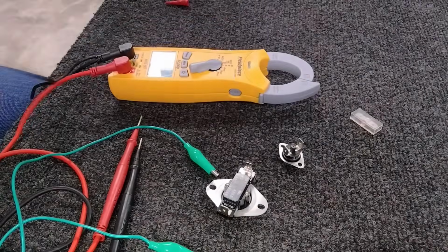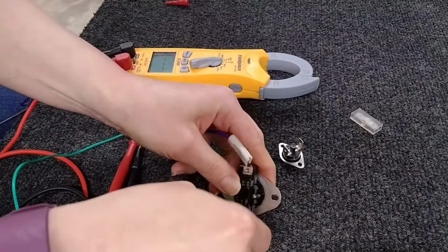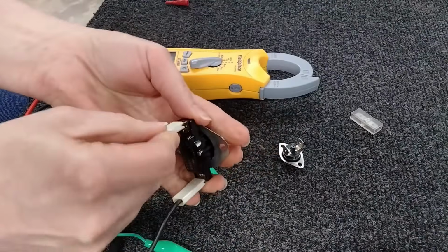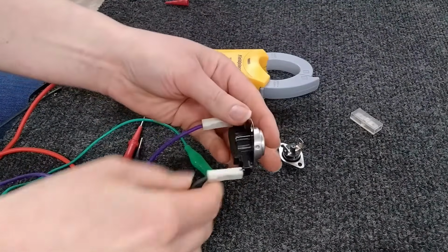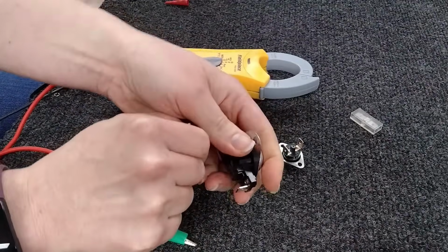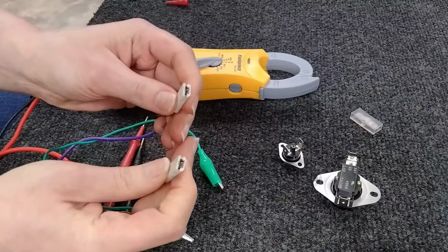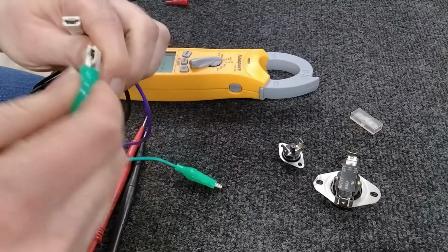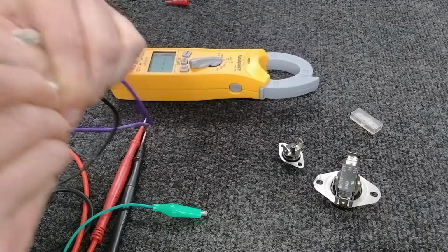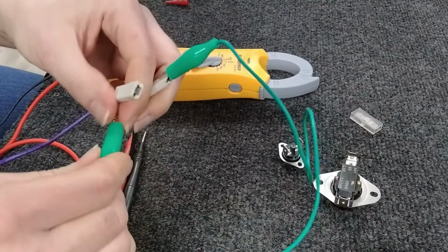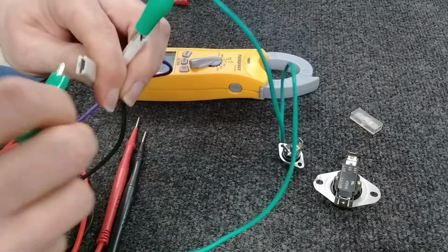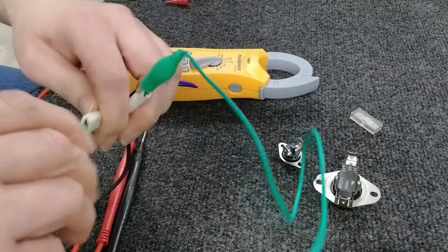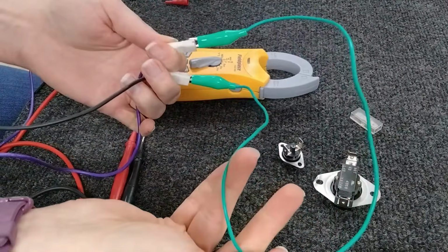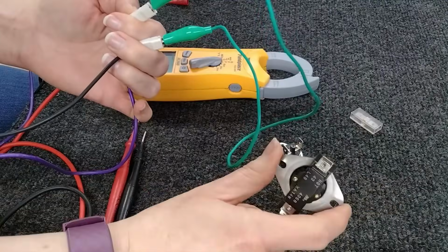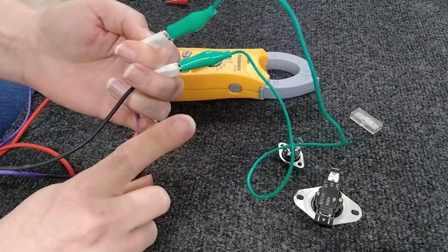Pull your wires off, because they're going to be connected here on either side. Great. So you're going to remove those wires, and what this is doing is closing the circuit yourself. Here we can just hook our gator clips on there, and these next ones are super annoying because they've got these little insulated tabs on them, which is super fun to try to hook anything on. And now we've effectively closed our circuit. So it's going to bypass your limit switch while you're testing. Do not leave it like this. It's a safety hazard.